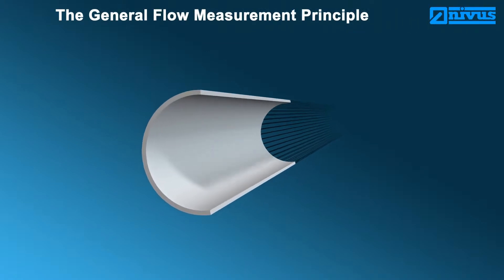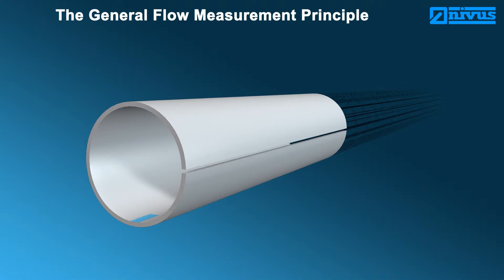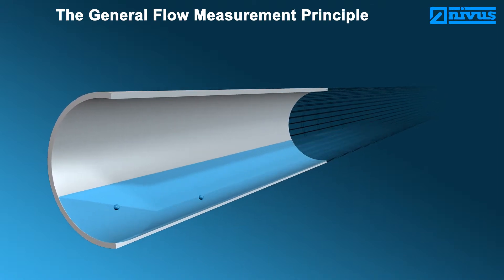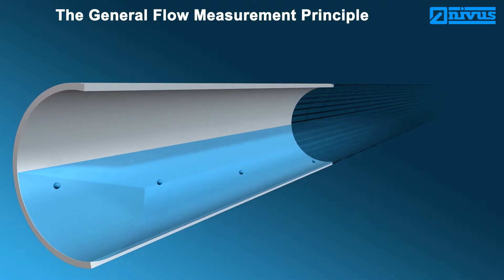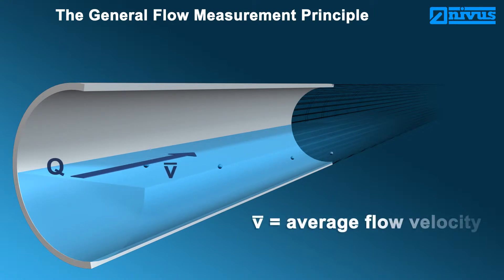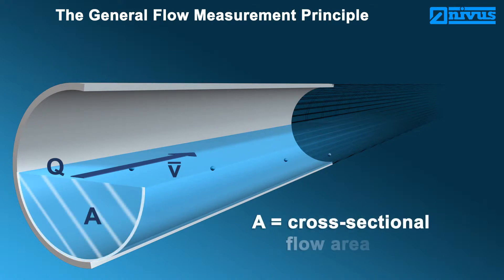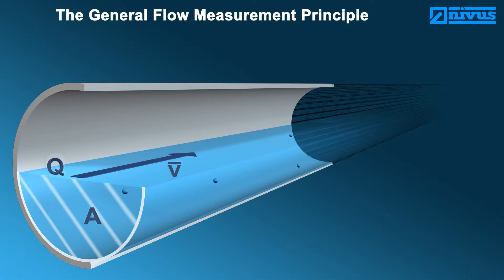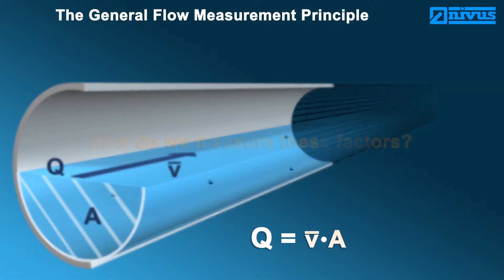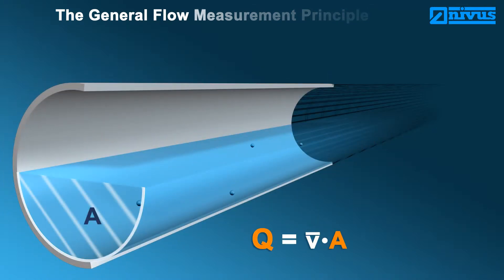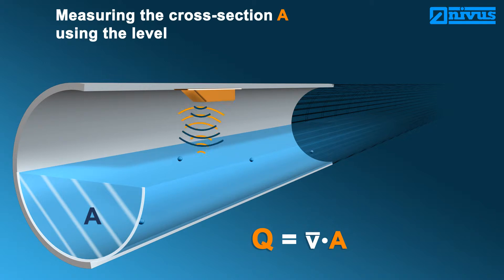The flow measurement principle. Flow cannot be measured directly. There are various factors required to detect the flow Q, such as the average flow velocity and the flow cross-section. From this, the general formula is obtained: Q equals V average times A. The flow cross-section A is determined by continuously measuring the level in consideration of the channel shape.